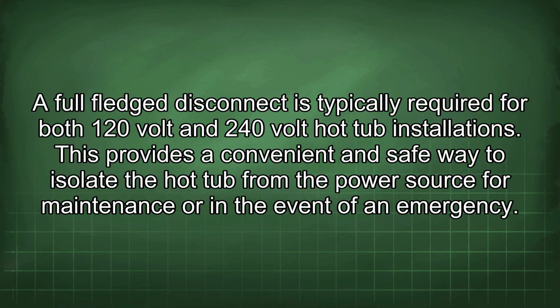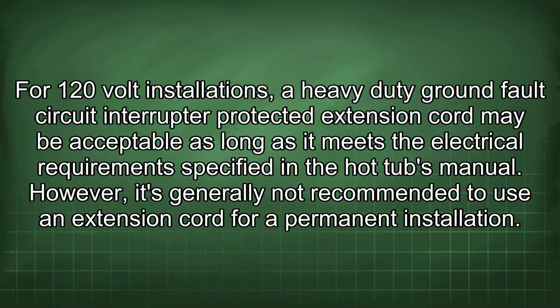A full-fledged disconnect is typically required for both 120 volt and 240 volt hot tub installations. This provides a convenient and safe way to isolate the hot tub from the power source for maintenance or in the event of an emergency. For 120 volt installations, a heavy-duty ground fault circuit interrupter protected extension cord may be acceptable as long as it meets the electrical requirements specified in the hot tub's manual. However, it's generally not recommended to use an extension cord for permanent installation.